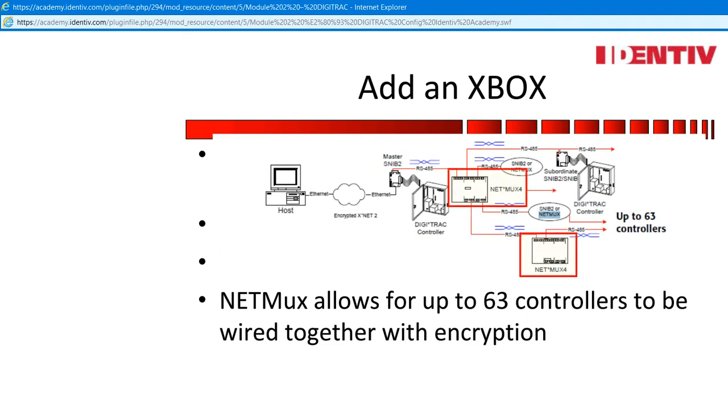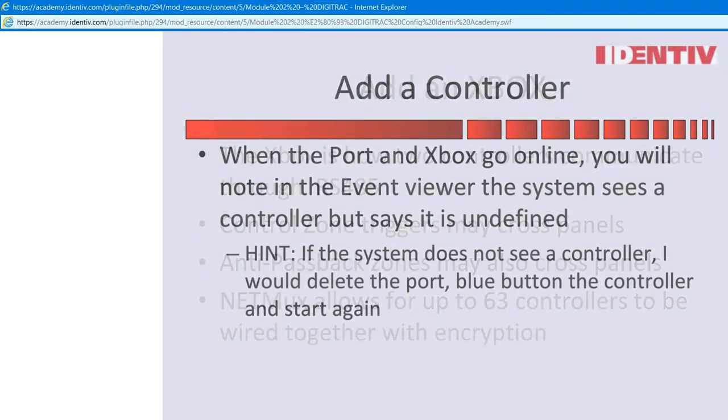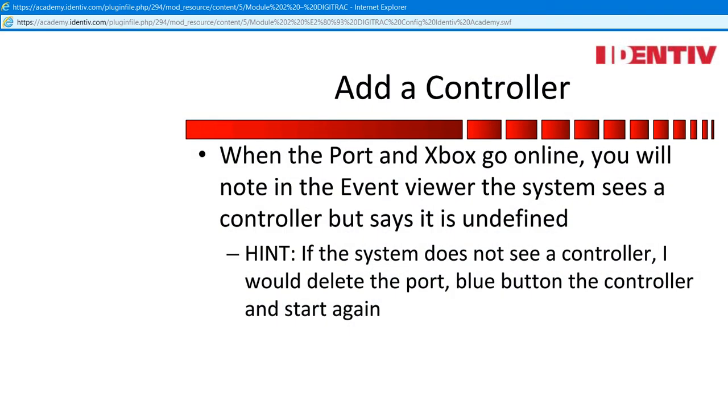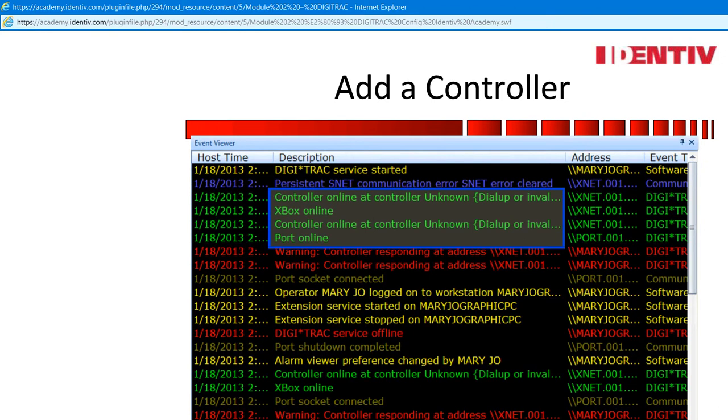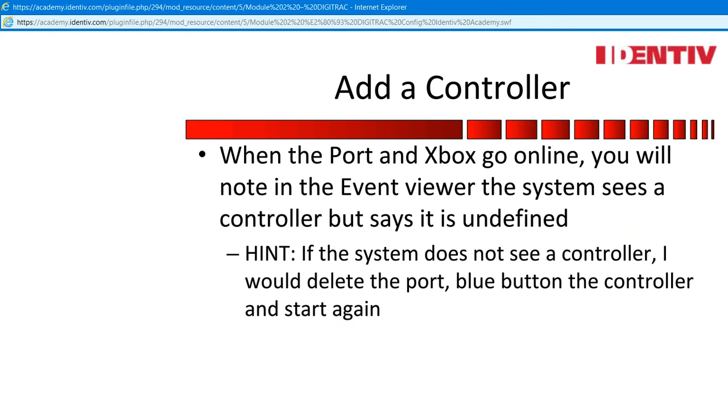My suggestion is to just turn on the Xbox switch when addressing the SNIB2 — it will remind you to add the Xbox when creating a port and also enable the function if you are wiring multiple controllers together. The NetMux is a device that repeats the signal to controllers downstream and can allow one master SNIB to broadcast to one or all other controllers. When deciding how to wire up controllers, think of this option. Add a controller. When the port and Xbox go online, you will see a note in the event viewer that the system sees a controller but it is undefined. If the system does not see a controller, delete the port, blue button the controller, and start again.